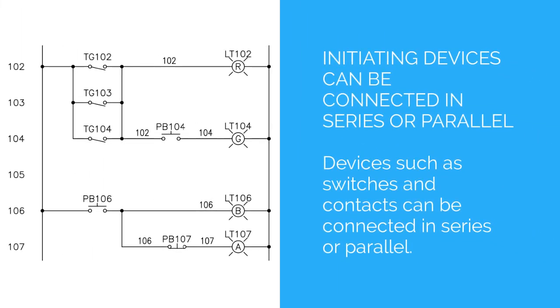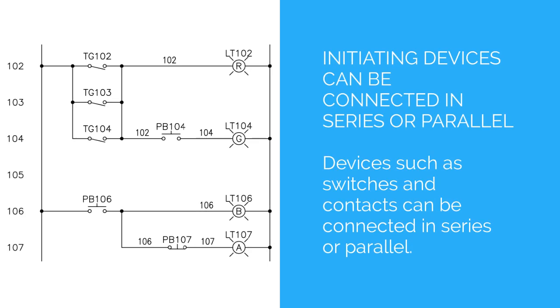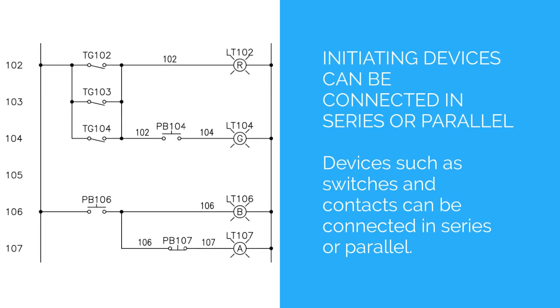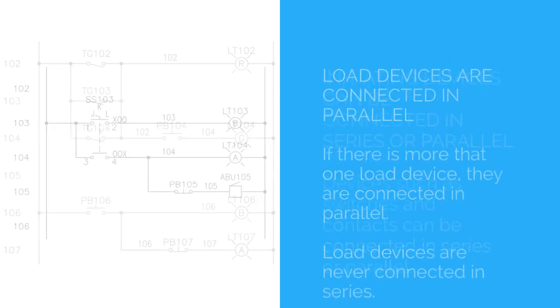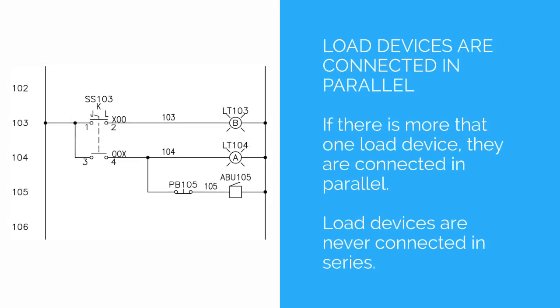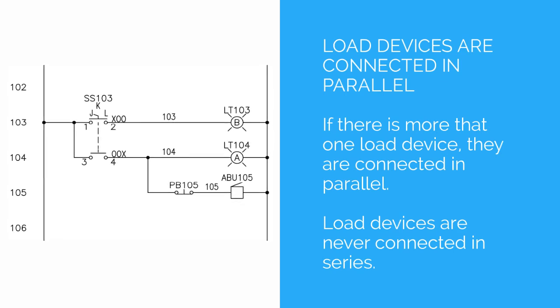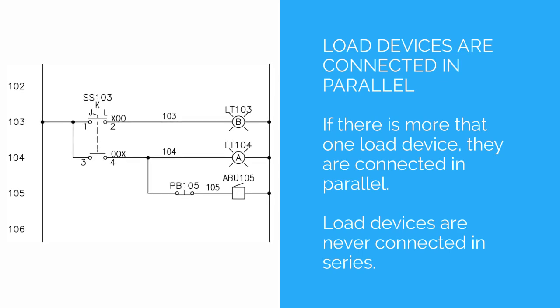Initiating devices can be connected in series or parallel. Devices such as switches and contacts can be connected in series or parallel. Load devices are connected in parallel — if there is more than one load device, they are connected in parallel. Load devices are never connected in series.